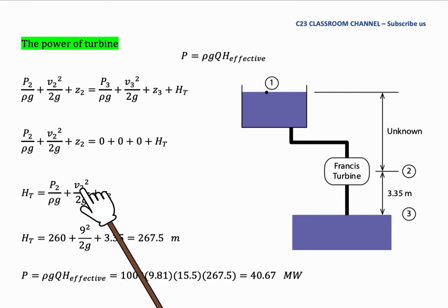The velocity V2 is nine meters per second. And the value of Z2 here is equal to - I'm sorry, the Z2 here is 3.35 meters. So we could calculate the value of head of turbine here is equal to 267.5 meters. After this, we could calculate the power of turbine by using this equation. And then we substitute all the values here. And then we get it is around 40.67 megawatts.